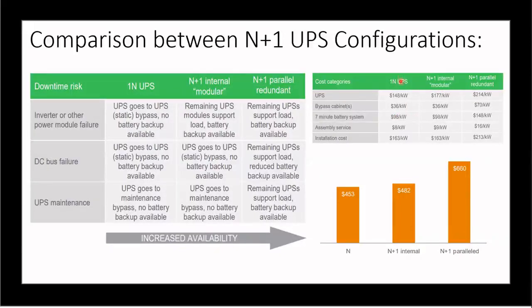Now, there is also the cost difference here. If we are buying a UPS with no redundancy, then obviously it will cost less. If we are doing N+1 internal modular redundancy, it will be a little bit more. If we do parallel, definitely it will be more, because we are using 3 to 4 UPSs. But it also depends on the scenario, on what kind of redundancy the customer is looking for. If they want to save money, then they should go with the internal modular. But if they want more redundancy and more reliable power, then they should definitely focus on this, right?